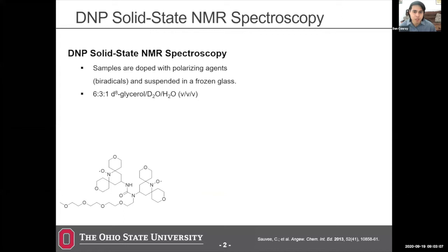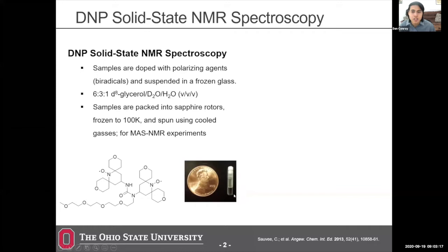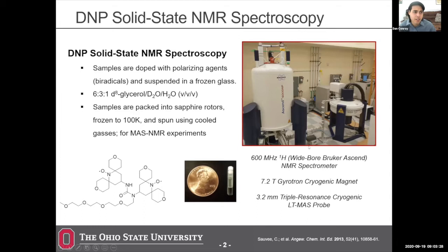We pack samples into sapphire rotors, frozen down to 100 Kelvin, and spin them for essentially normal MAS NMR experiments. Here at Ohio State we have a 600 MHz NMR coupled to a gyrotron that generates high-power, high-frequency microwaves sent along a transmission line. Cooling gases get the sample down to 100 Kelvin via a liquid nitrogen cabinet.